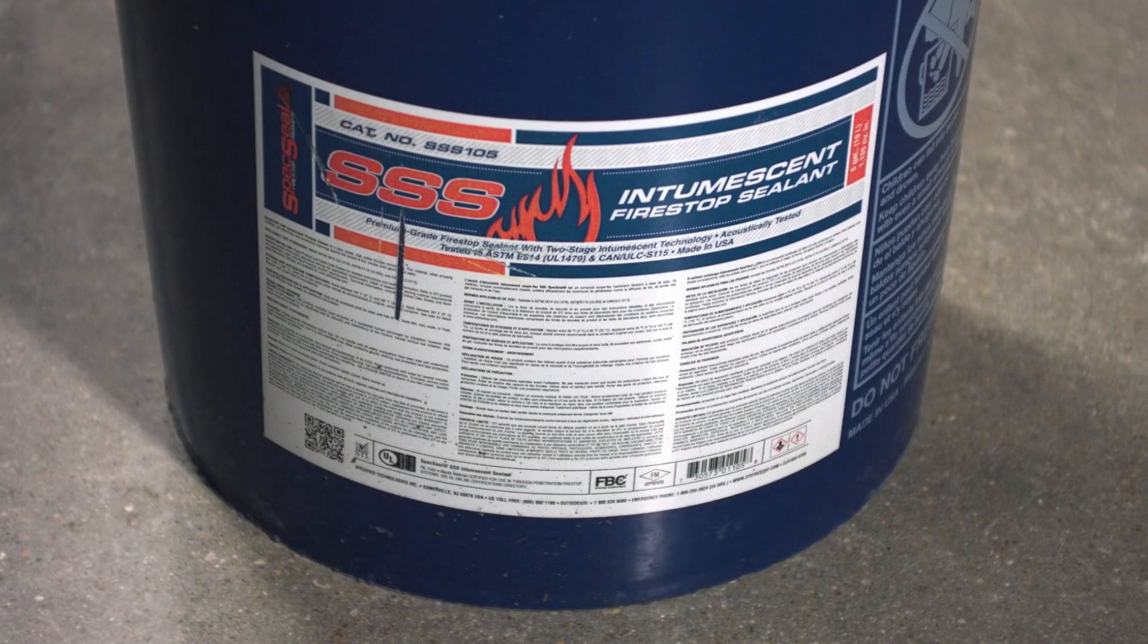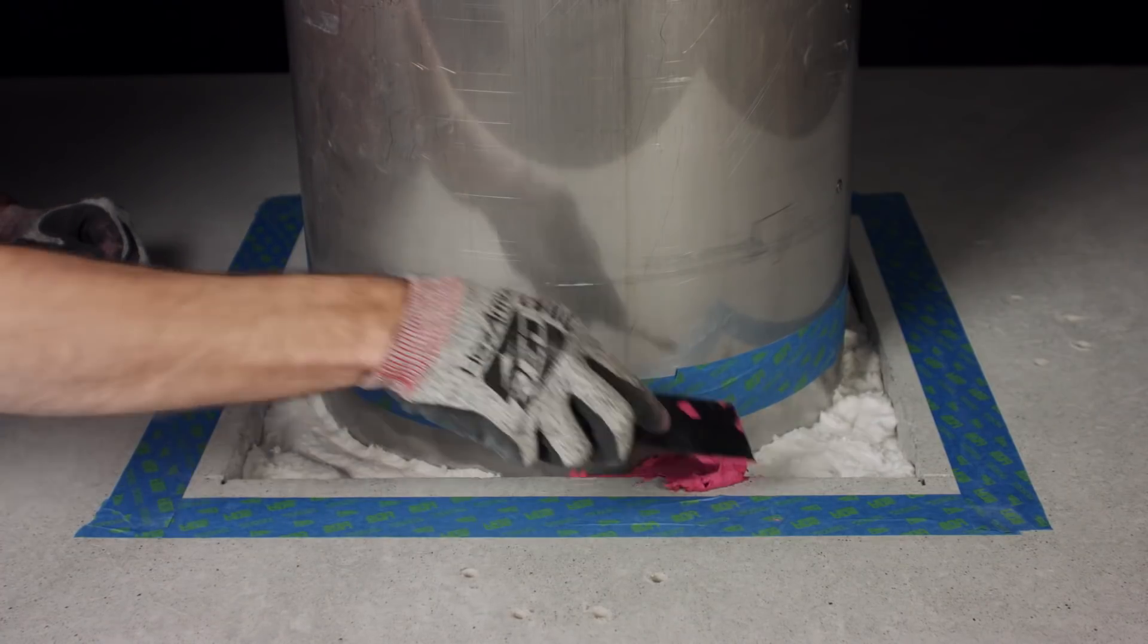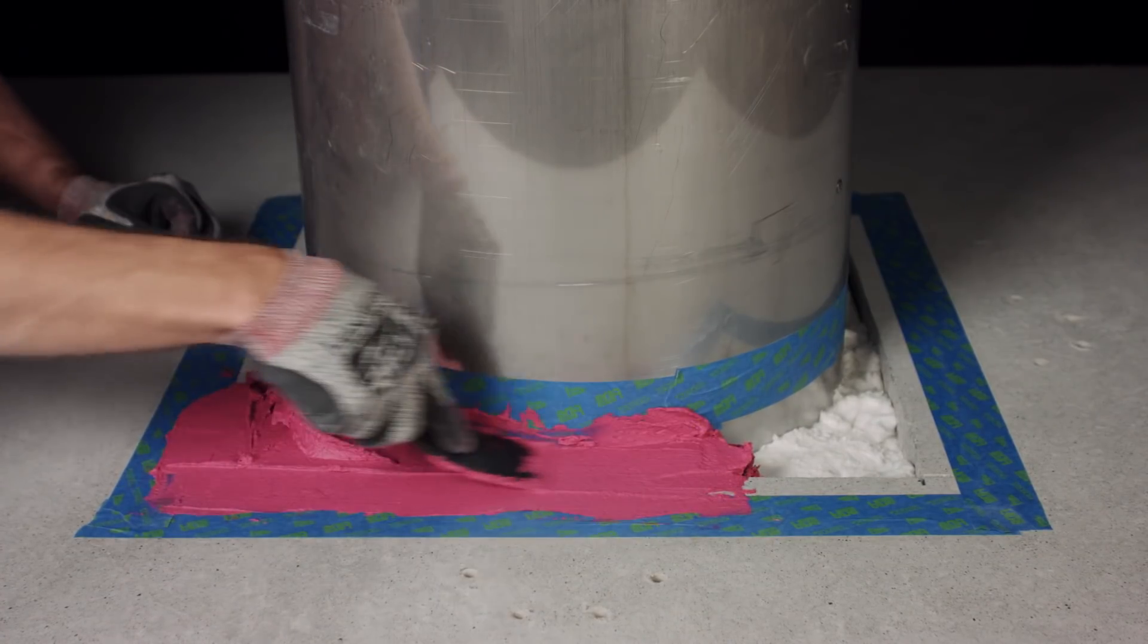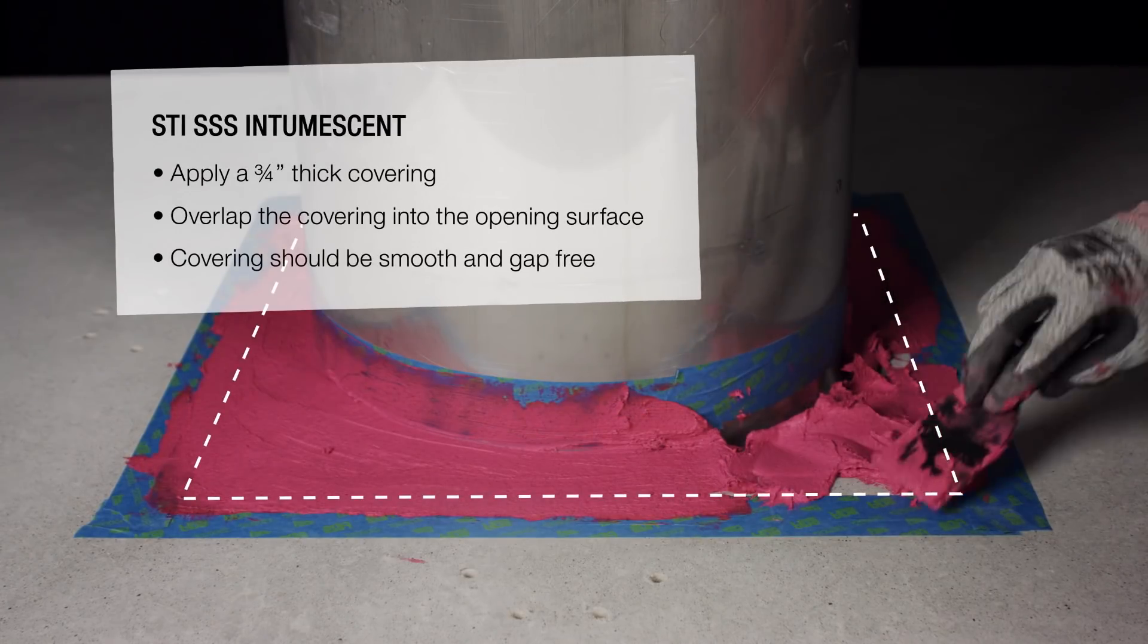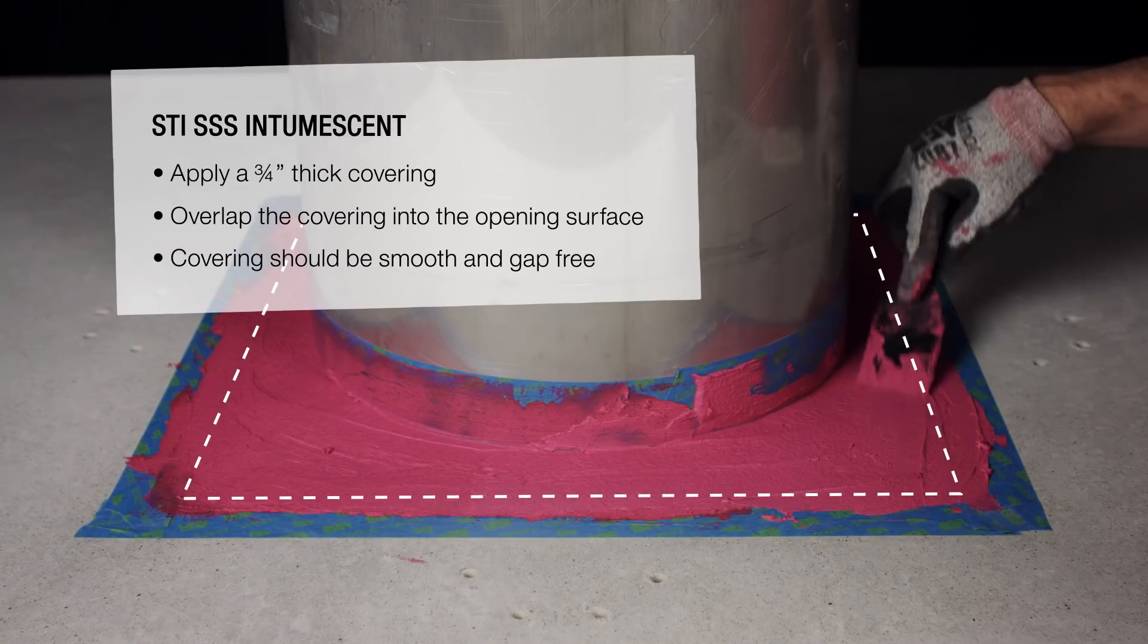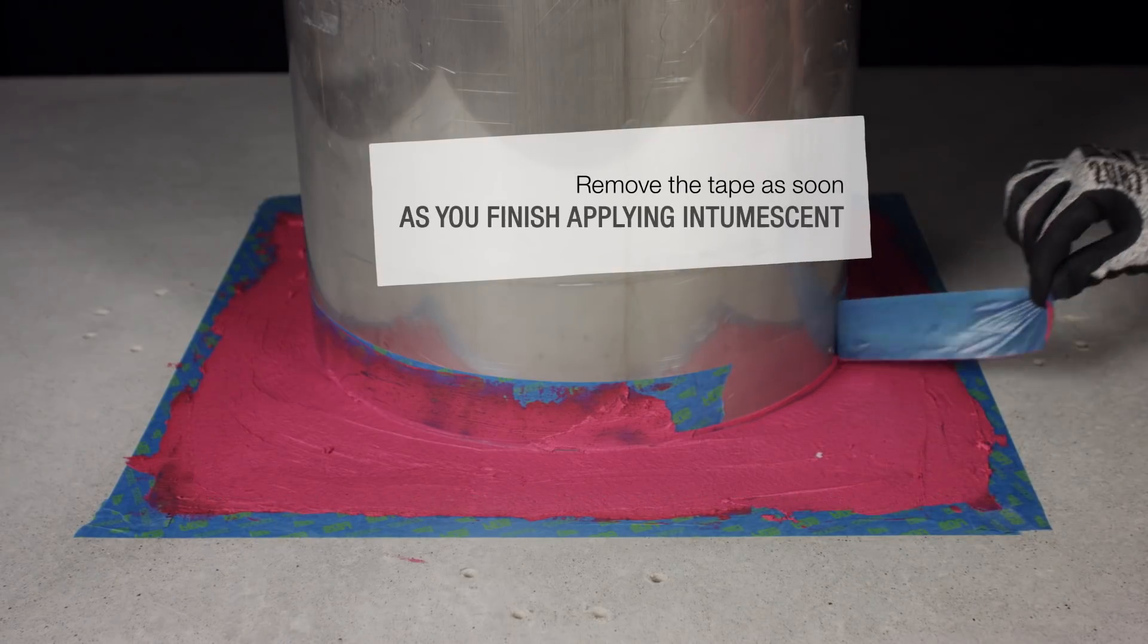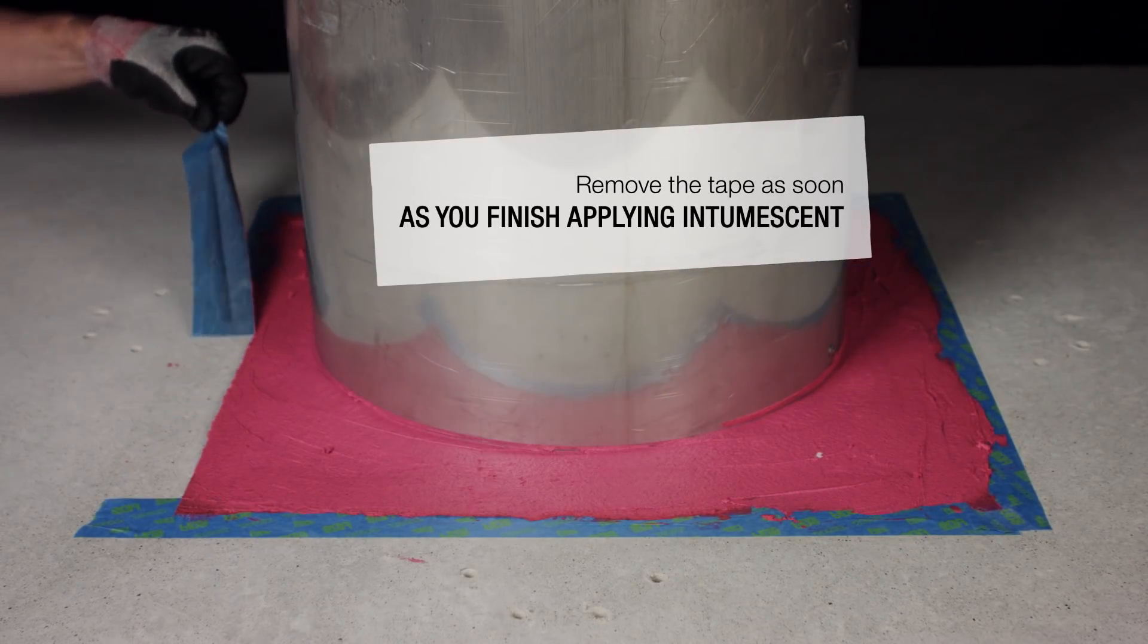Using intumescent, fill the remaining three quarter inch gap so that the surface is level with the floor. The intumescent should overlap onto the floor or ceiling, ensuring that there are no gaps between the edges of the opening or the duct's outer shell. Remove the tape as soon as you're finished applying the intumescent.